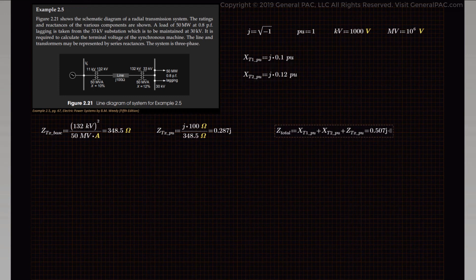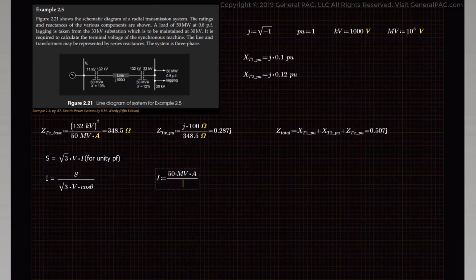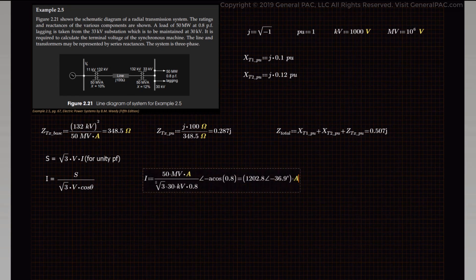Next, we will determine the current that should be flowing in the power system and into the load if the load has to be maintained at 30 kV. The apparent power equals the square root of 3 times the voltage times the current. We rearrange this formula and add the power factor correction: current equals apparent power divided by the square root of 3 times voltage times power factor. With 50 MVA divided by the square root of 3 times 30 kV times 0.8 power factor, we get a current value of 1203 amps at an angle of negative 36.86 degrees.